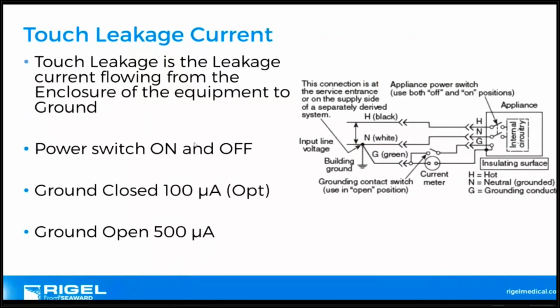Touch leakage. So again, if I'm going to do nice drawings out of it, if you do have this fault condition, so that earth is open, the fault current will flow through this way, and this is where we pick up. This is the body model effectively. This is how we pick up these, dielectric or capacitance, stray capacitance within the device. One major difference between NFPA 99 and 62353 and 60601 is you do testing in on and off positions of the device, whether that's soft switching or hard switching of the medical equipment. Ground closed is now optional. Ground open is mandatory.